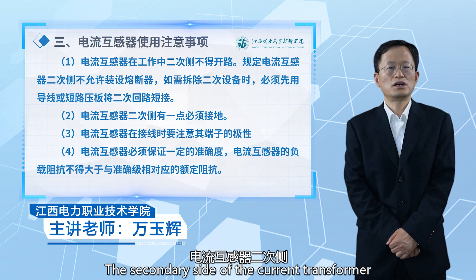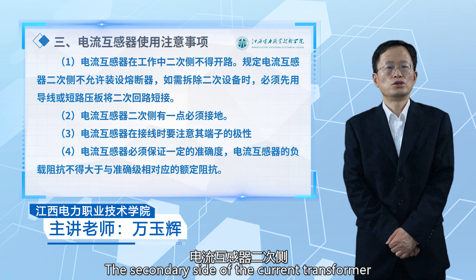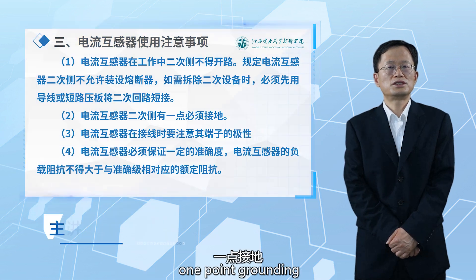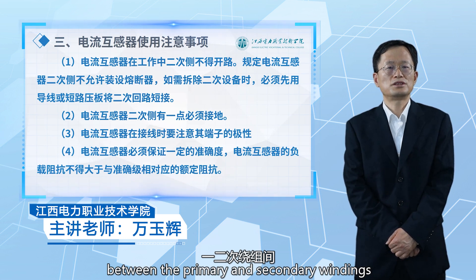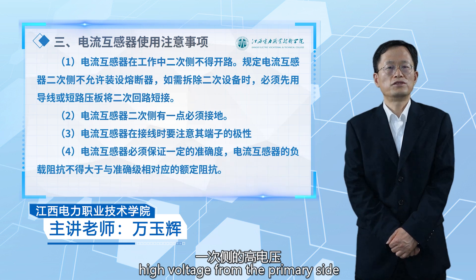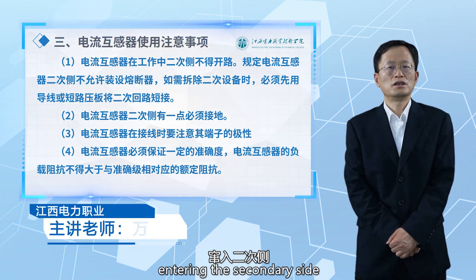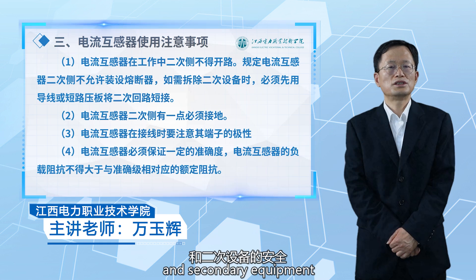The secondary side of the current transformer must have one point grounded. This grounding prevents breakdown of insulation between the primary and secondary windings, which could allow high voltage from the primary side to enter the secondary side, endangering the safety of personnel and secondary equipment.